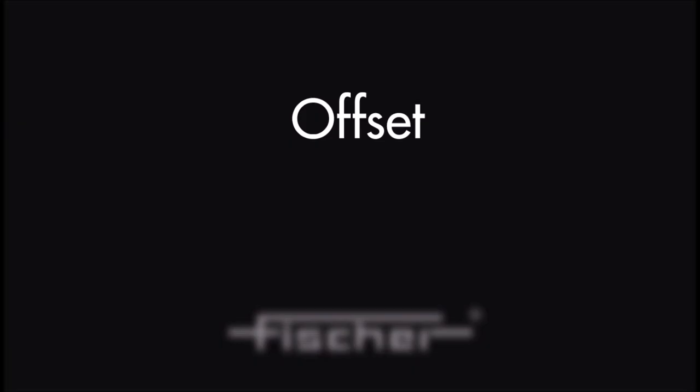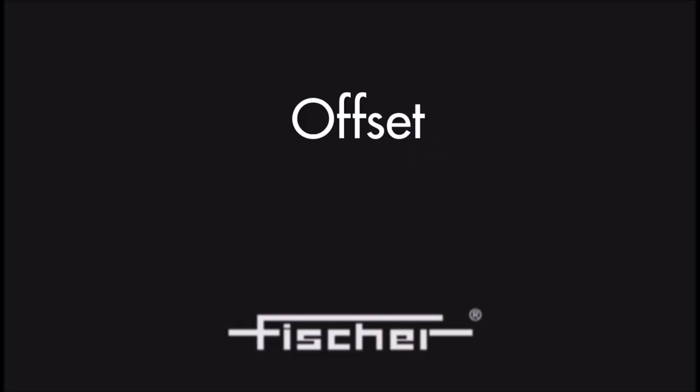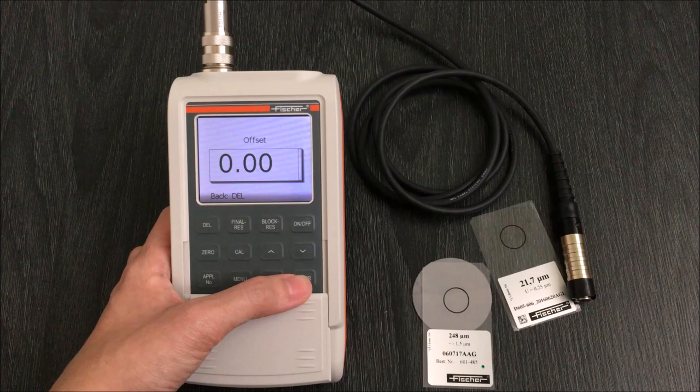Offset is a feature available to automatically subtract an offset value from the actual measurement reading. This can be used when you only want to measure the paint coating when there is a zinc layer below it.